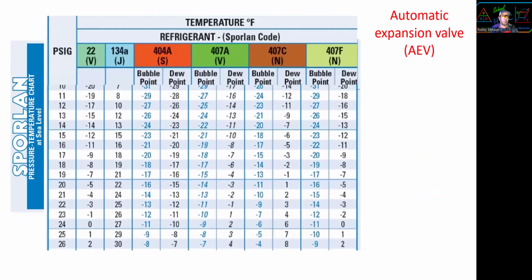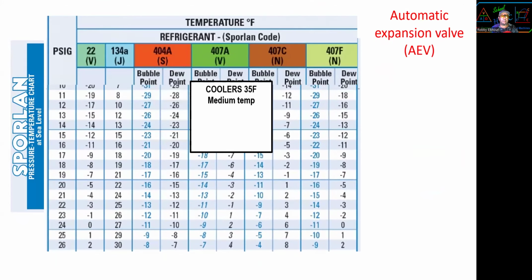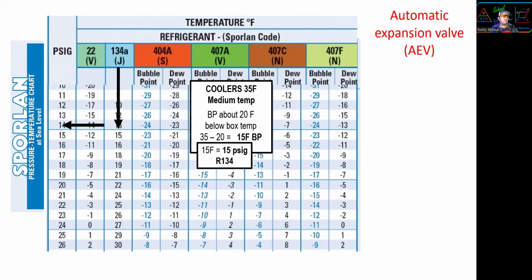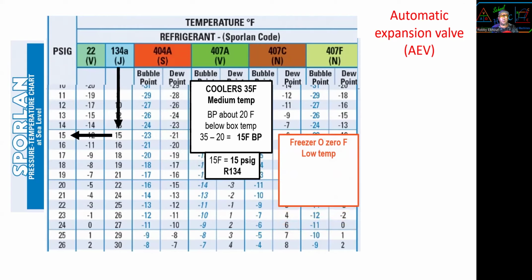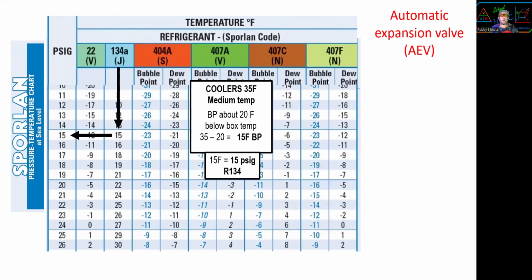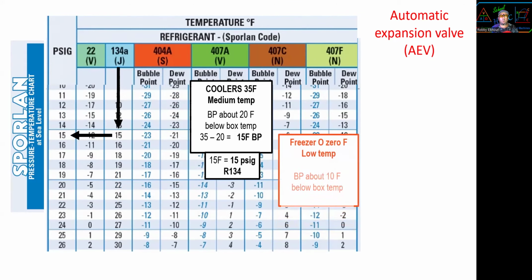All right, now PT chart. Medium temp, R134a, medium temp, 35-degree temperature. Boiling point should be about 20 degrees below. 35 minus 20, we need 15-degree boiling point. Sounds right. R134a is easy. 15 pressure equals 15 temperature equals 15 pressure. Freezer 0 degrees. So I set my automatic expansion valve until my pressure is 15 and forget about it. We're good to go.